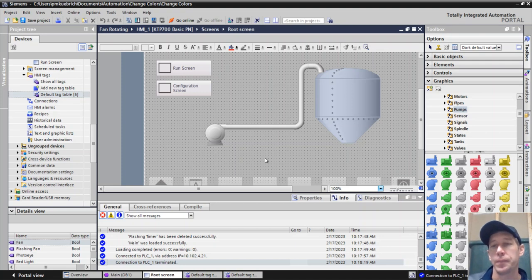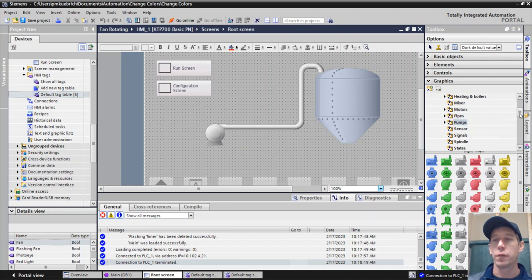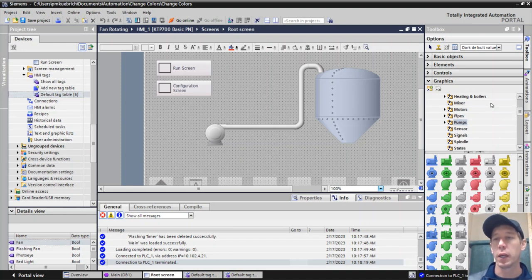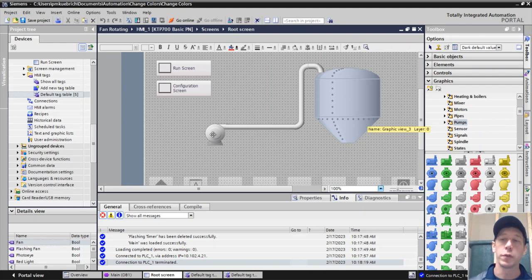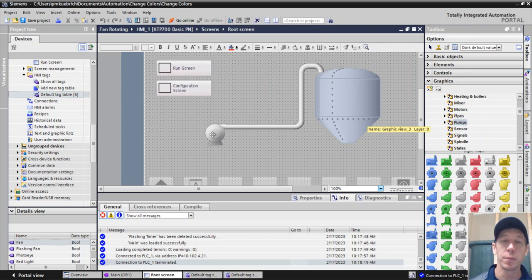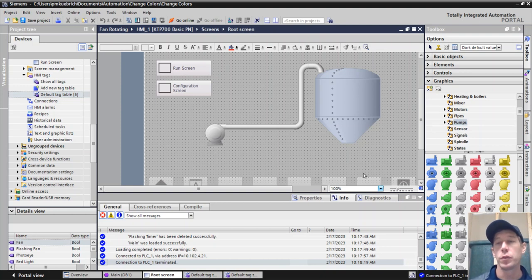So a couple different factories, manufacturers, plants will have different color schemes. One the ISA really likes to show is gray meaning off and good because we want to only have colors when something changes. Other factories will have red meaning off, green meaning on. So it depends on what particular application you're looking for.